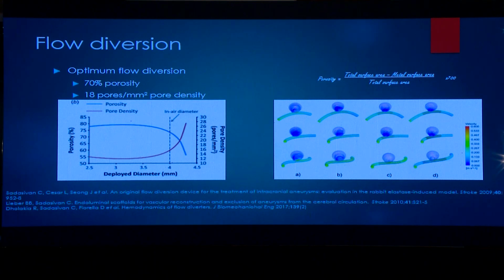Note that both the pore density and the porosity of the stent are only partially designed-in features of the stent, and there is considerable ability to vary that by stent sizing selection and the interaction between the stent, the vessel wall, and the aneurysm neck at the time of deployment. However, it must be noted that there is a minimum amount of metal surface coverage that is required to achieve flow diversion, and any less metal coverage than that will not result in meaningful flow diversion.